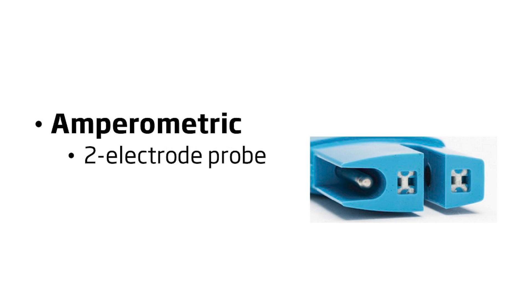Two-electrode probes work through two electrodes that are isolated from each other, but in such a way that they can maintain contact with the sample at the same time. They're made from non-reactive materials, such as stainless steel or graphite. The materials need to be non-reactive so the probes do not have side reactions with the sample, but also so that they do not degrade when in contact with the sample. The two electrodes pass a current at a specific frequency through the sample. Remember what we talked about earlier with ions? That comes into play here. The more ions you have in your sample, the lower the resistance you will have for the current to reach the other electrode. This will result in a higher conductivity reading.